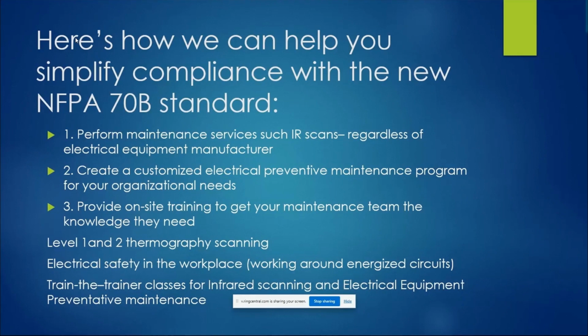Because there are devices like little infrared scanner filters that snap over your smartphone, which are, for all intents and purposes, infrared scanning equipment. But the problem is they're not calibrated and not tested to a standard. They're great tools and fun to use, but they won't meet the requirements of the NFPA 70B standard. Make sure the equipment you use, whether Fluke, FLIR, or whoever, specifically meets the ASTM standards specified inside the NFPA 70B standard.